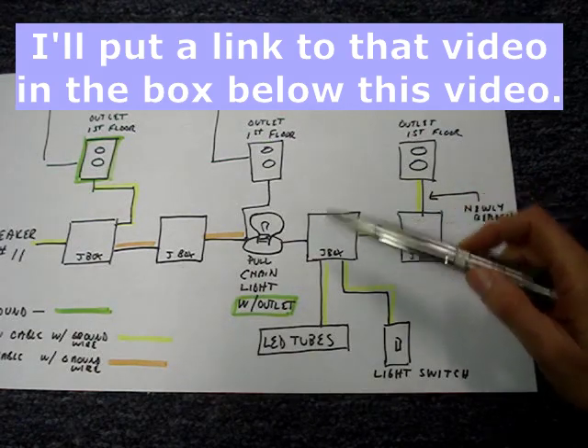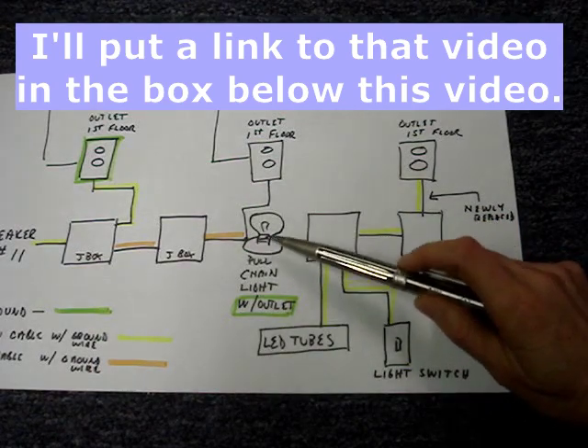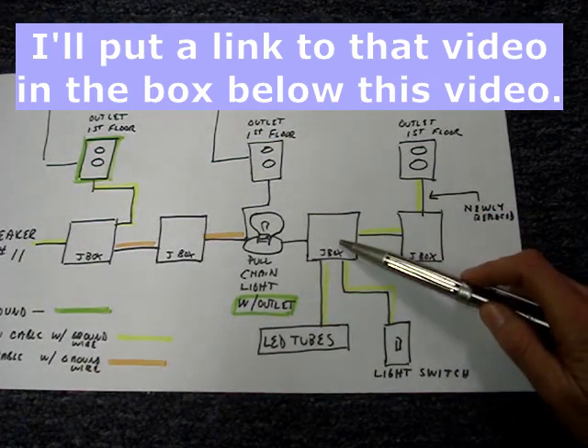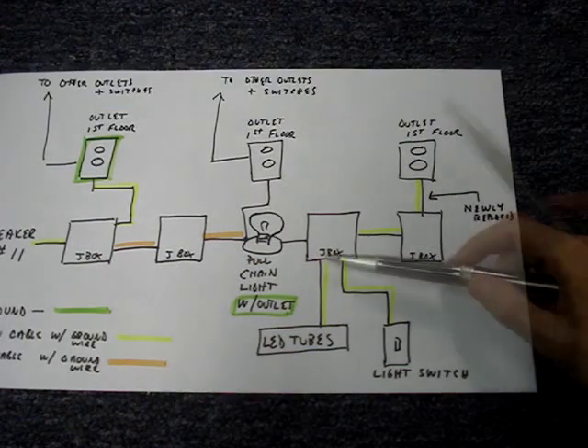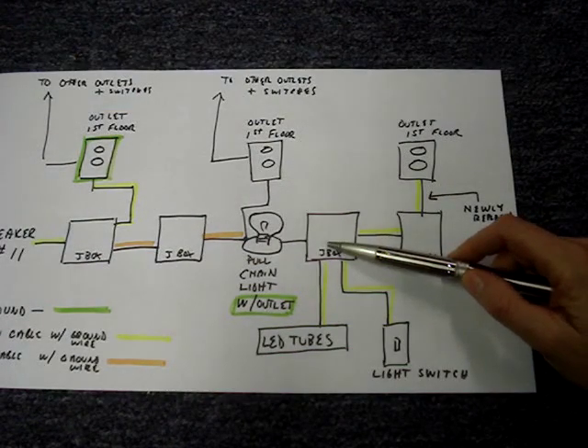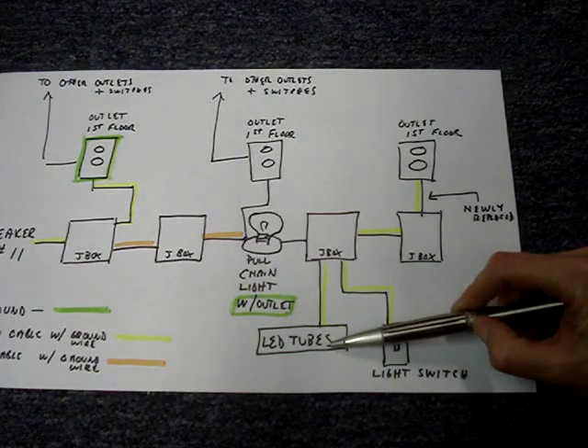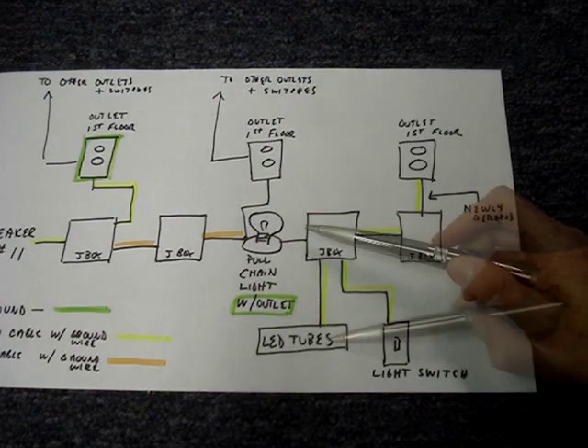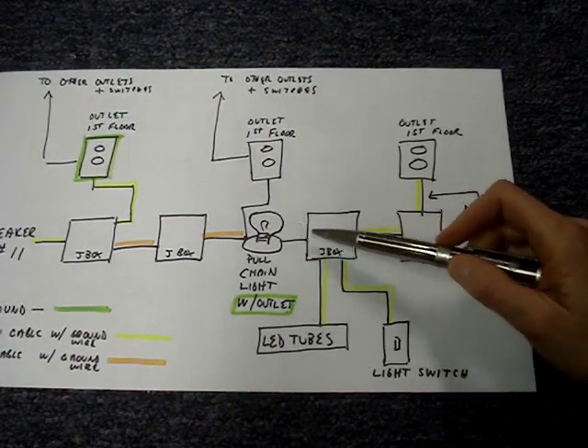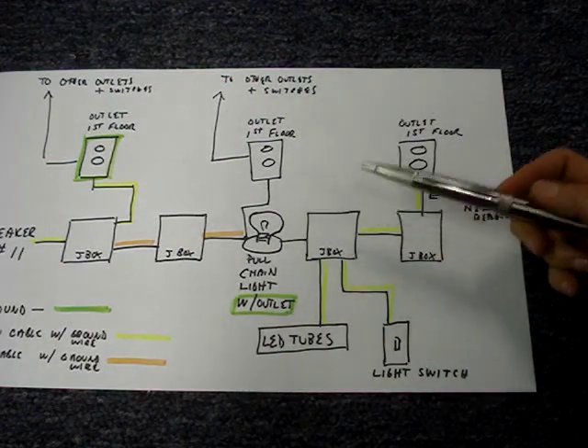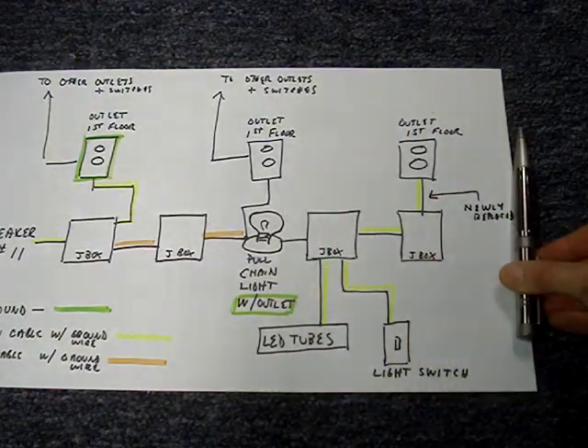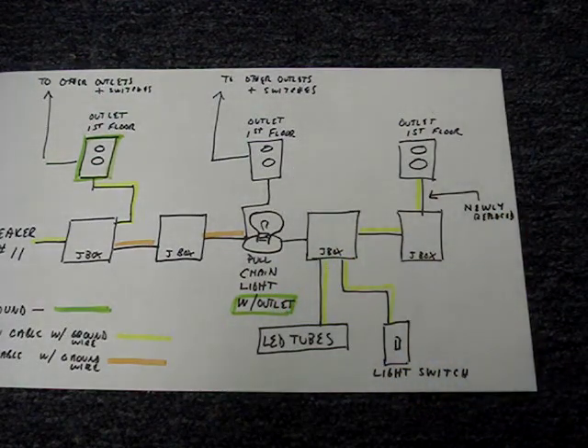On the video previous to this one, I was troubleshooting a missing ground. I discovered that the cable that goes from the pull chain light to this junction box does not have a ground wire, and this junction box is the one that I showed you in the very beginning of this video. It has voltage on it. There's a plug that leaves this junction box. It connects an LED tube light. That tube light is disconnected. If I don't have a ground wire coming into this junction box, then I know that the problem has to be from here over, because I suspect that the black or the hot wire is connected to the ground wire.